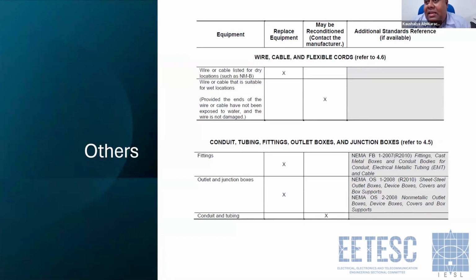after checking what has happened and up to what level it has affected, you may be able to use them under inspection by a competent person. Fittings, outlets, junction boxes, all to be replaced. Conduits and tubing, yes, you can use, but if they contain more water and have difficulty drying, you may seek another distribution path.